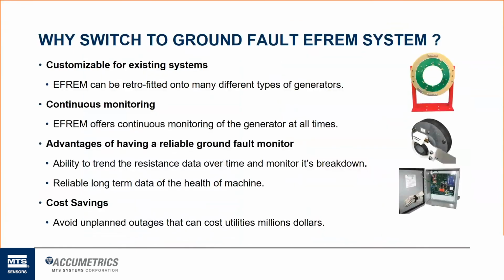So again, why switch to our ground fault system? Customizable, that's really the biggest thing. That's the thing we're trying to push most in this presentation, is that we offer that ability to retrofit many different types of generators and exciters that are out there that may or may not have a ground detection system on them. So that's really the market that we go after, is competing with other companies that already have a system, and we're replacing it with something much better and much more accurate. It gives you that continuous monitoring at all times of the generator.